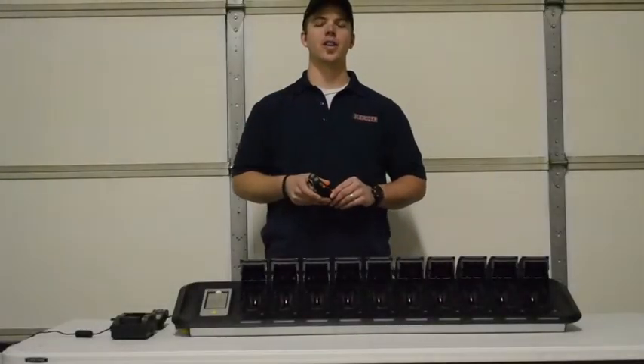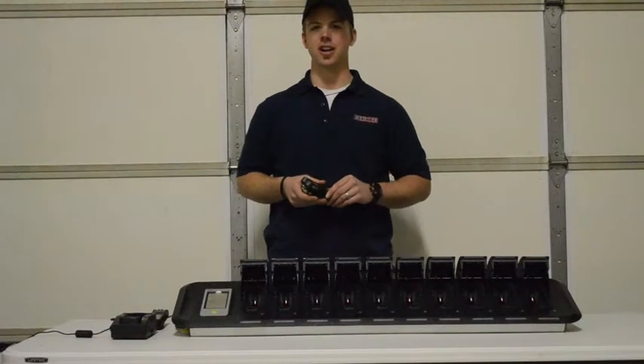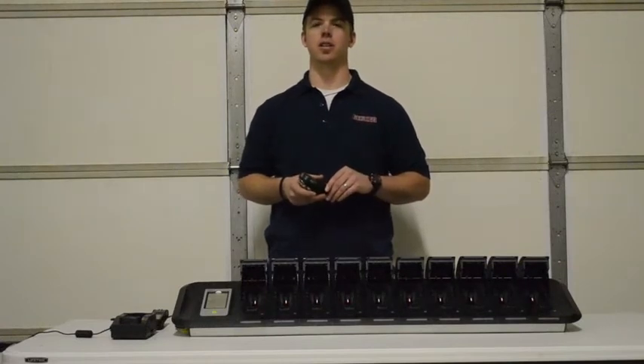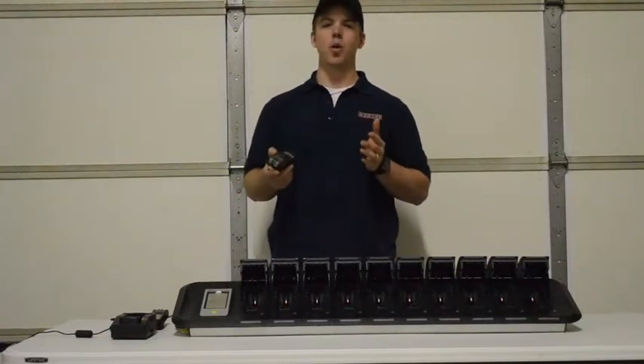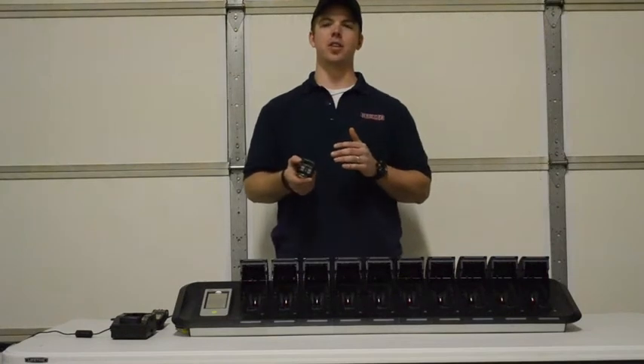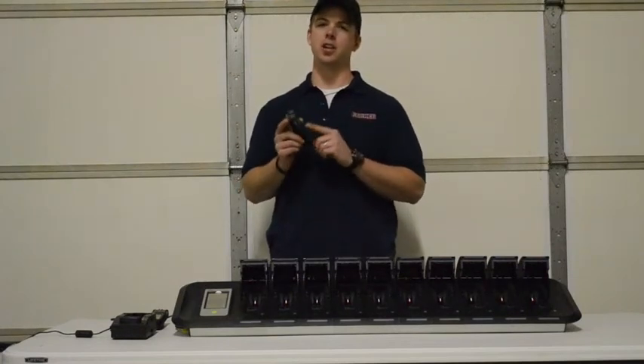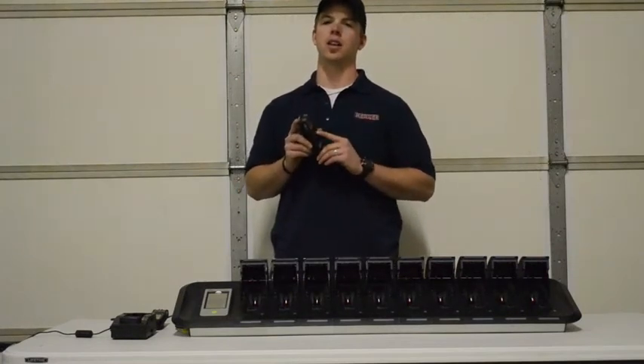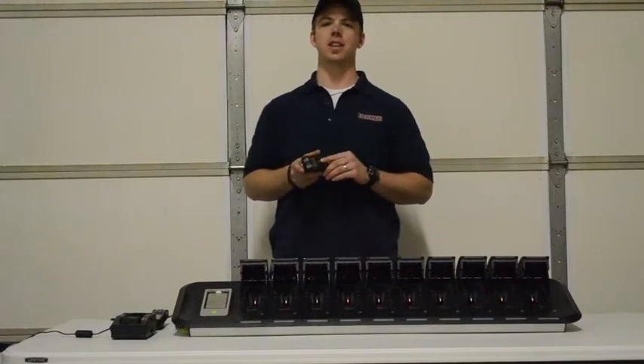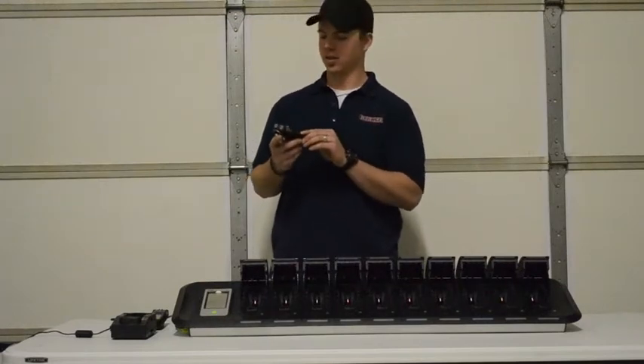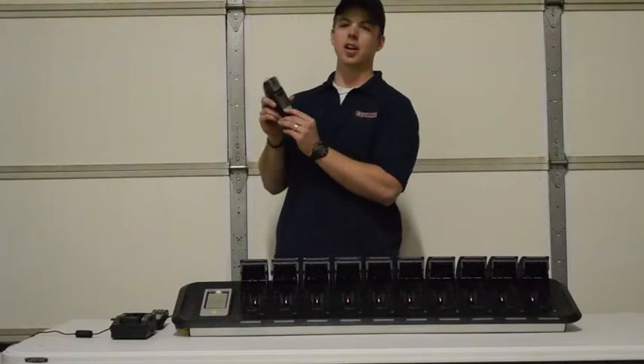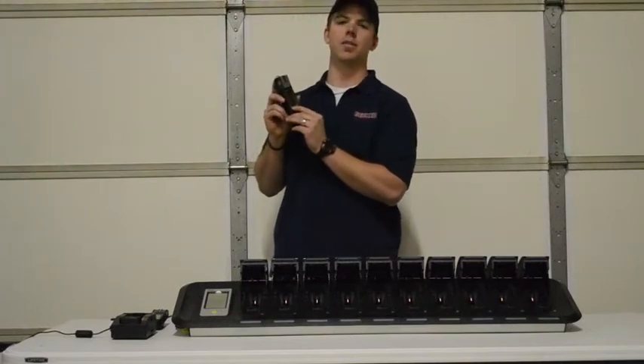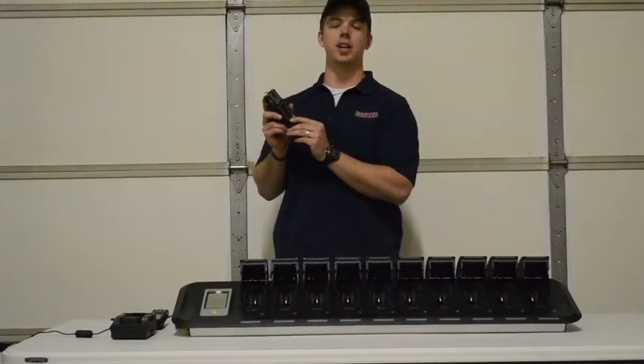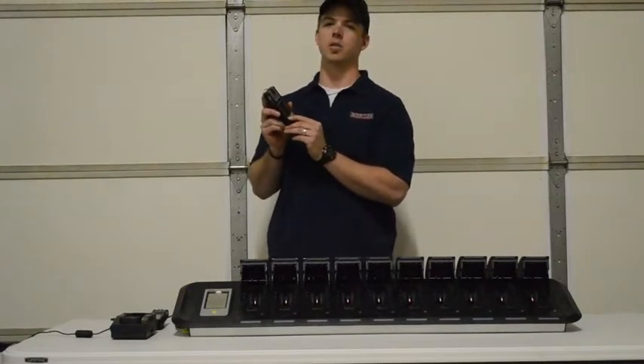Now I'll be showing you how to do a fresh air calibration on your XM2500 gas monitor. It's important to know for the first 5 minutes after you turn on your monitor, there will be an exclamation mark at the top right corner. This is normal. This means that the sensors are warming up. To do a fresh air calibration, make sure that you're in a fresh air environment. If you're not in a fresh air environment, after the fresh air calibration, your sensors will go into negative.